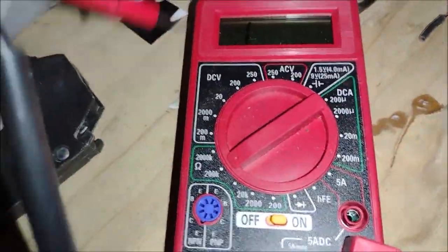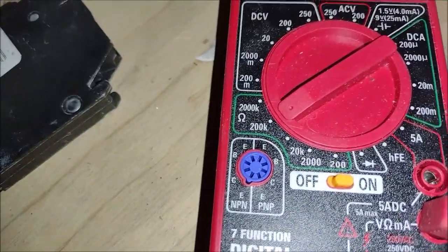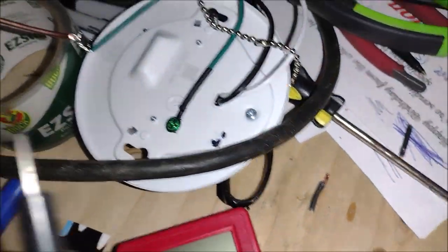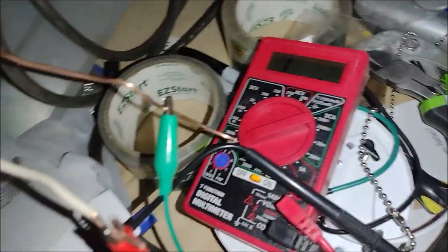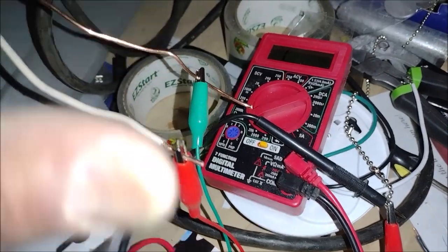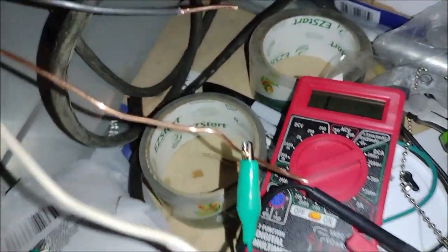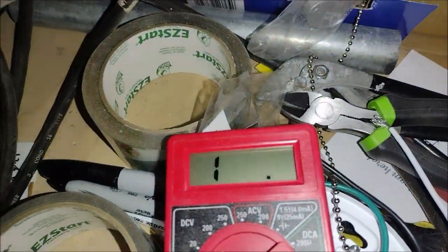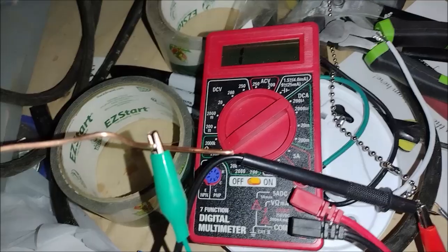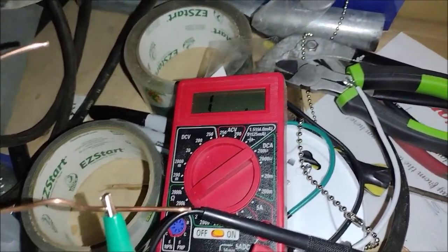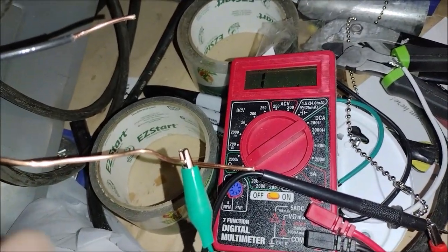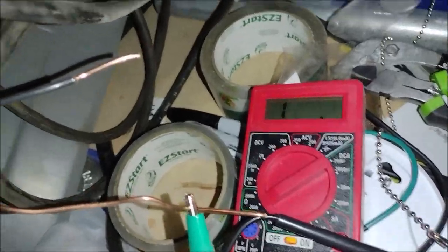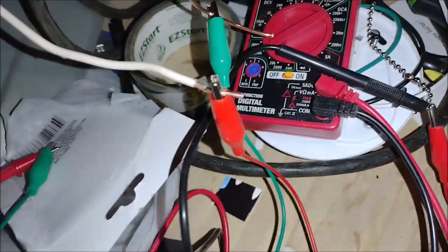So we have the ohm meter set on the ohm, and we are measuring the continuity between each of these two wires when the switch is on or off. We are measuring the ohm or the continuity between each of these two wires with the copper. We should have an open circuit, which means there should not be continuity when we turn the switch on or off. If you have continuity, it means the ground or the neutral is connected to one of these wires, which means you have a short.